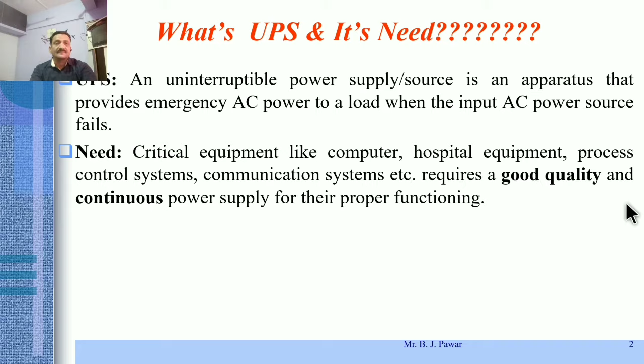Now, the classification of UPS. Basically it is divided into two types, as already shown: offline type of UPS and online type of UPS. Again, there are subtypes: offline preferred type and offline interactive under the offline type, and under the online type there is the online preferred type. So offline UPS means what? When AC mains directly supplies the power to the critical loads and simultaneously charges the battery, which is kept as a backup supply.